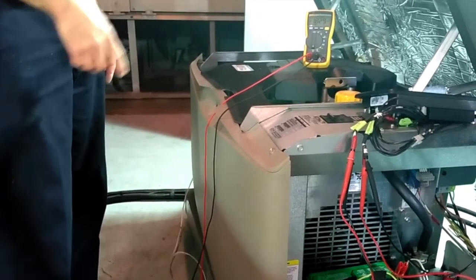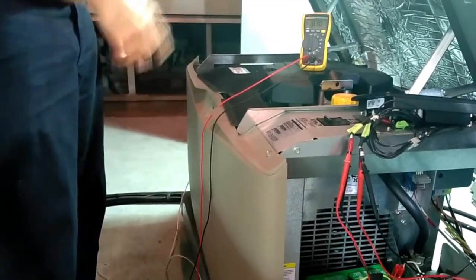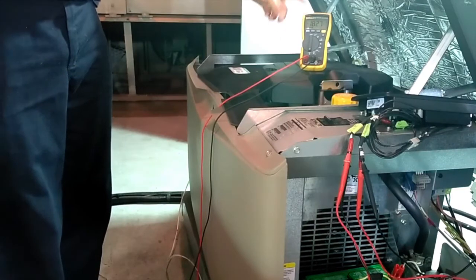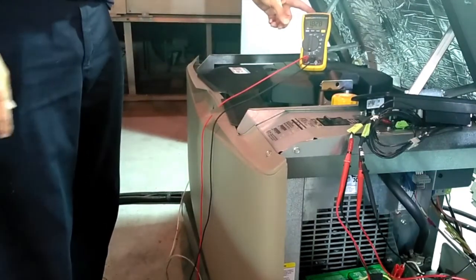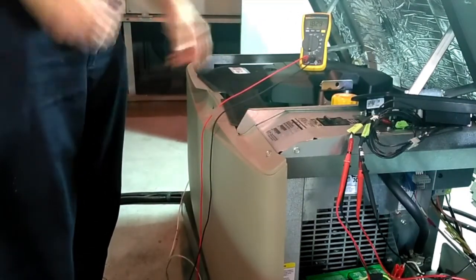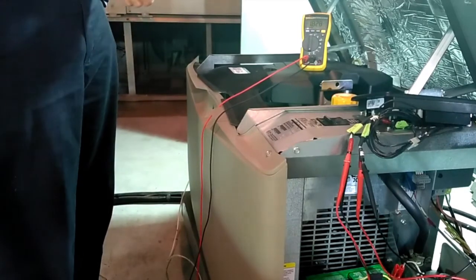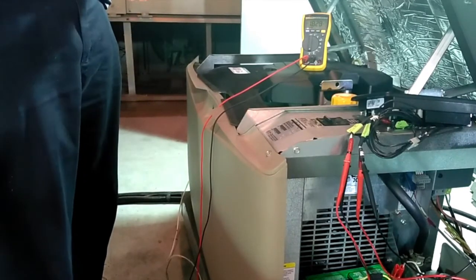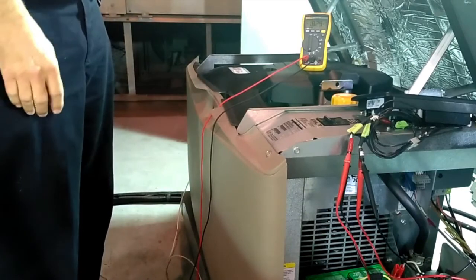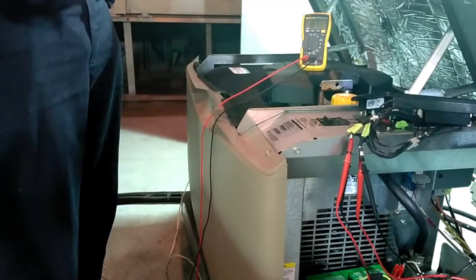So now what we're going to do is we're going to start the generator, and we're going to monitor our amperage to the rotor. That should stay stable, shouldn't change. If that amperage drops off to 0, we have a running open. If it starts climbing and going high, we have a running short, and we have a rotor issue that we'd have to investigate and possibly change the rotor.